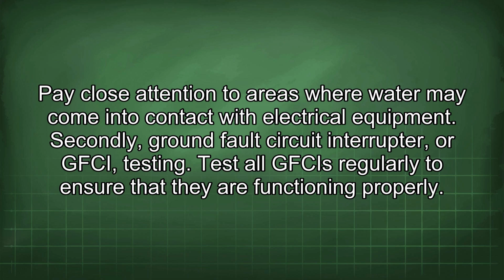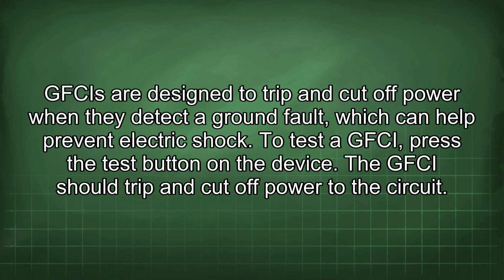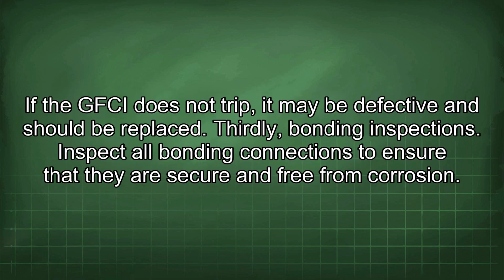Secondly, ground fault circuit interrupter, or GFCI testing. Test all GFCIs regularly to ensure that they are functioning properly. GFCIs are designed to trip and cut off power when they detect a ground fault, which can help prevent electric shock. To test a GFCI, press the test button on the device. The GFCI should trip and cut off power to the circuit. If the GFCI does not trip, it may be defective and should be replaced.